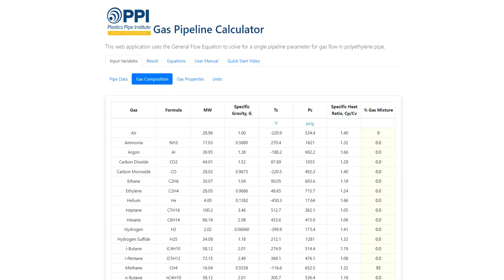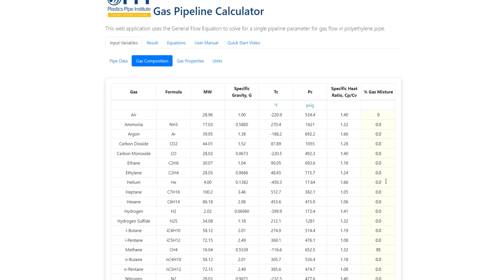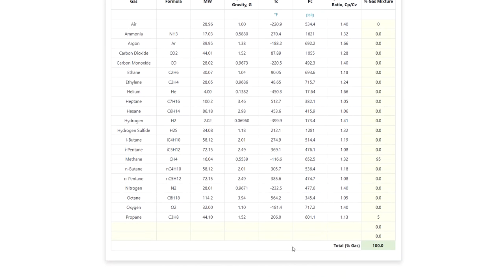The pipeline efficiency of flow is set to 95%; this value can also be changed. Next, the composition of gas must be entered after clicking the gas composition tab. A percentage of different gases can be entered as long as they total to 100%. Fields at the bottom of the table allow the user to enter variables for gas that may not be in the table. The gas mixture specific gravity, dynamic viscosity, and density are calculated from these gas percentages.